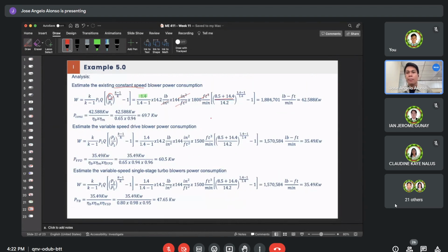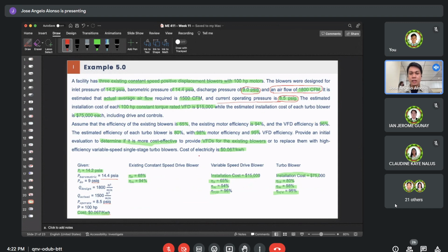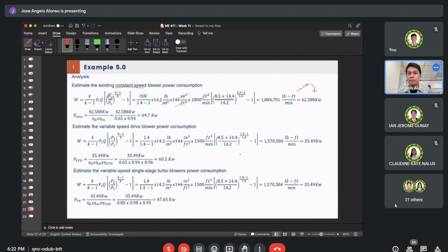Now we can calculate. The resulting unit here will be pound-foot per minute. Let's convert that into horsepower, and later into kilowatts. Why convert into kilowatts? Because our cost of electricity is $0.067 per kilowatt-hour, so it's more usable and preferable to use kilowatts rather than horsepower.